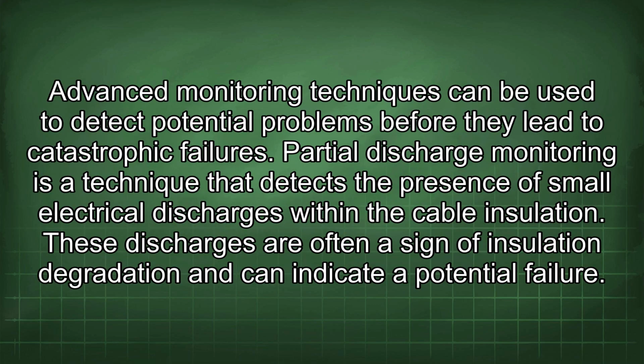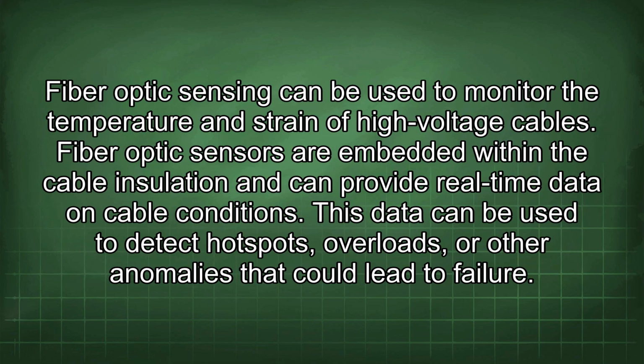Advanced monitoring techniques can be used to detect potential problems before they lead to catastrophic failures. Partial discharge monitoring is a technique that detects the presence of small electrical discharges within the cable insulation. These discharges are often a sign of insulation degradation and can indicate a potential failure. Fiber optic sensing can be used to monitor the temperature and strain of high-voltage cables. Fiber optic sensors are embedded within the cable insulation and can provide real-time data on cable conditions. This data can be used to detect hotspots, overloads, or other anomalies that could lead to failure.